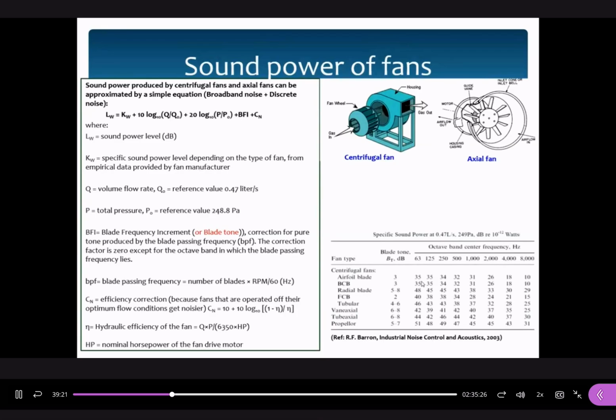Under what specific conditions? An airflow rate of 0.47 liters per second, and a pressure of 249 Pascal. There are two terms here: the second is Q0, the reference flow value taken as 0.47 liters per second (L is liters), and the reference pressure value is 248.8 Pascal, which we may also call P0. Under these two conditions, we measure the specific sound power level for different fan types.